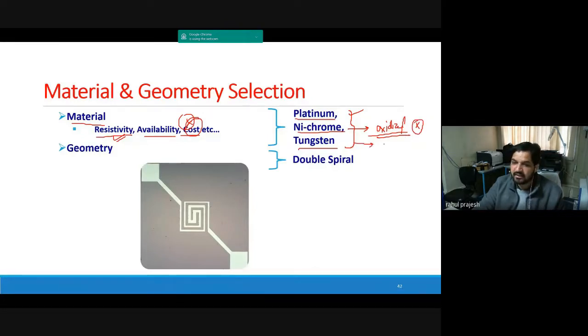Tungsten, on the other hand, also has a tendency to oxidize, but less. For precise applications, most of the time you use platinum because it's a noble metal and doesn't get oxidized. So the material will be stable, chemically and physically. If it is stable, it will give you very constant resistance, and hence you will get constant temperature for a long period of time.